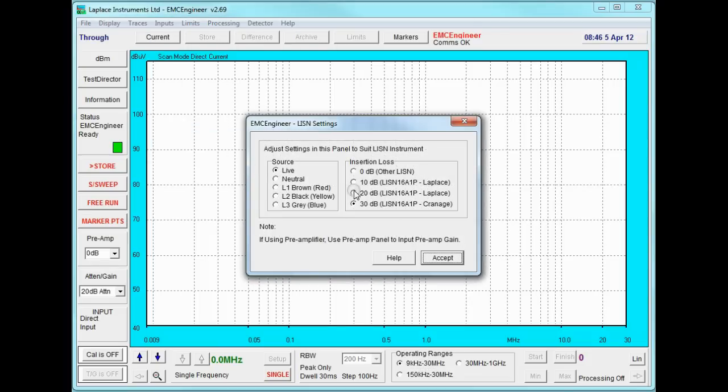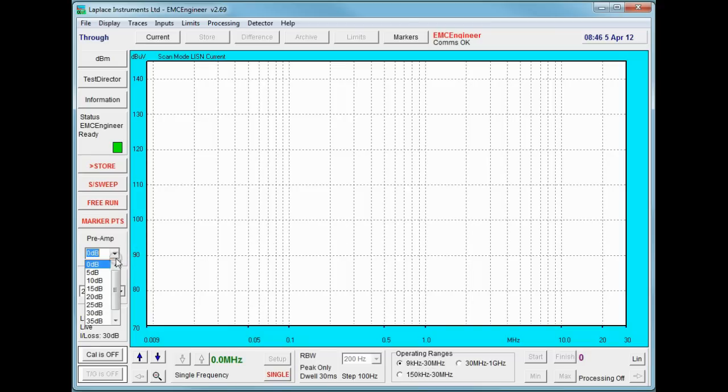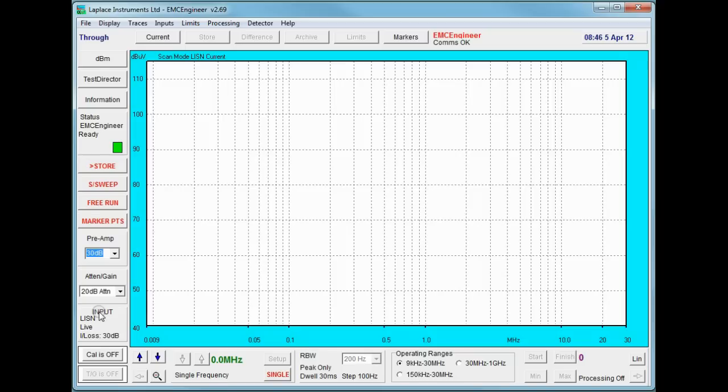Default LISN is the one we're using at the moment. And next set the fact that we have a pre-amplifier in circuit. This is a 30 dB pre-amplifier. And finally we need to set the attenuator level. If this is not set correctly, we will run the risk of overloading the analyzer and displaying distorted results.